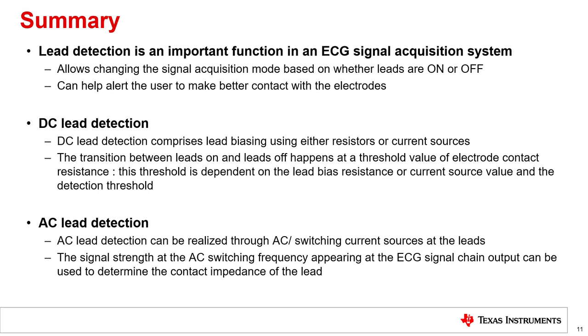DC lead detection comprises lead biasing using either resistors or current sources to bias the leads to a high or low potential, and comparators to distinguish between leads-on and leads-off condition. The transition between leads-on and leads-off happens at a threshold value of electrode contact resistance. This threshold is dependent on the lead bias resistance or current source value and the detection threshold. AC lead detection can be realized through switching current sources at the leads that generate an AC lead bias signal. The signal strength at the AC switching frequency appearing at the ECG signal chain output can be used to determine the contact impedance of the lead. Additional signal processing may be required to remove the AC lead switching frequency tone from the ADC output.